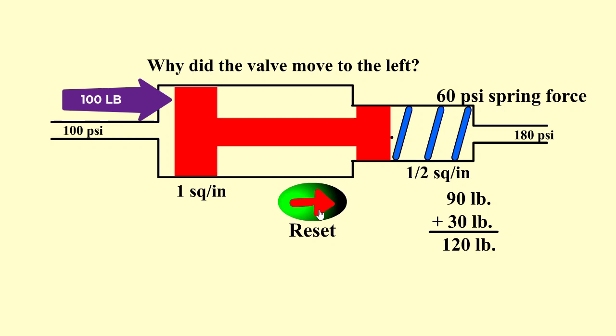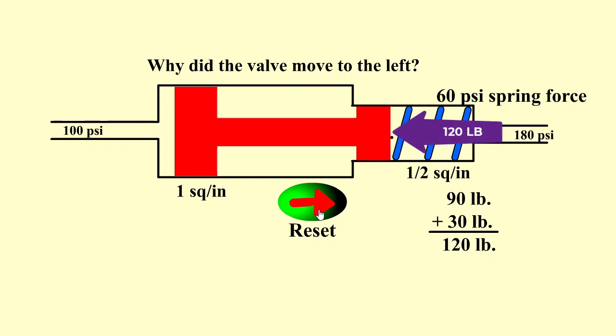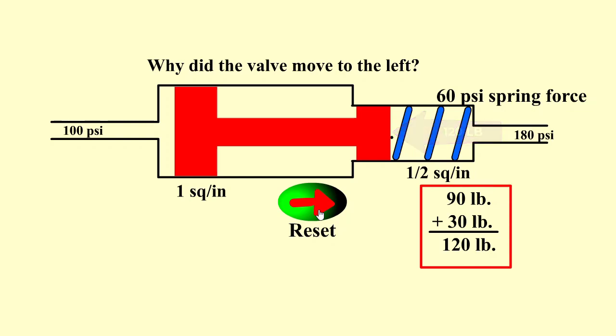We have 100 pounds of force on the left hand side trying to push it to the right. On the right hand side we have 120 pounds of force trying to push it to the left. We take the 90 pounds of force from the 180 psi of fluid pressure and add it to 30 pounds of spring force. That 30 pounds of spring force comes from 60 pounds per square inch applied to a half square inch — 60 times 0.5 is 30.